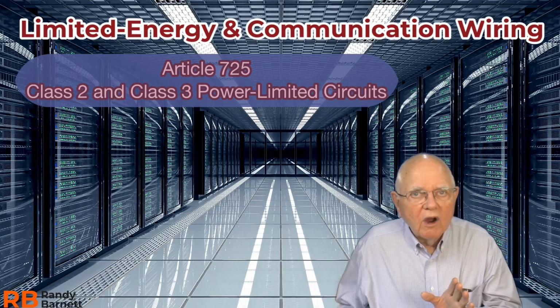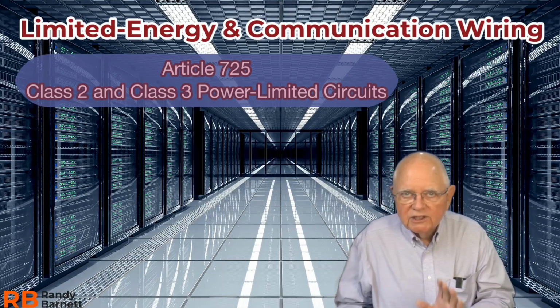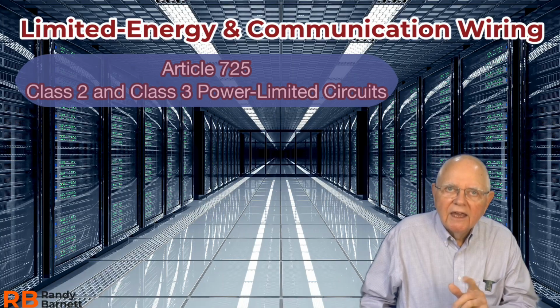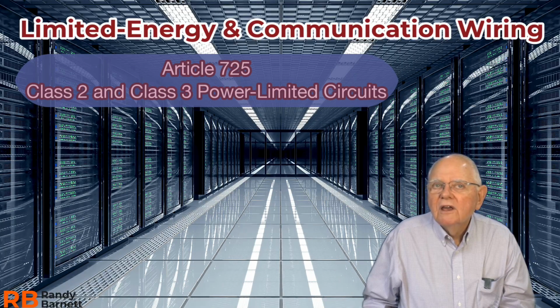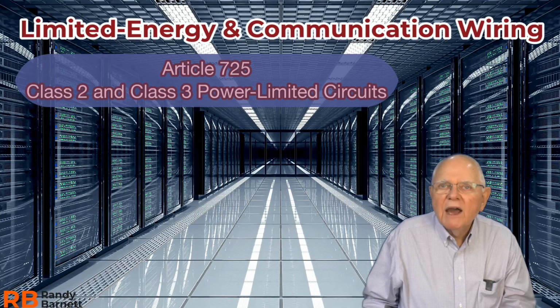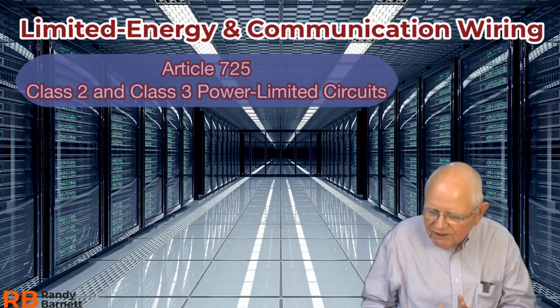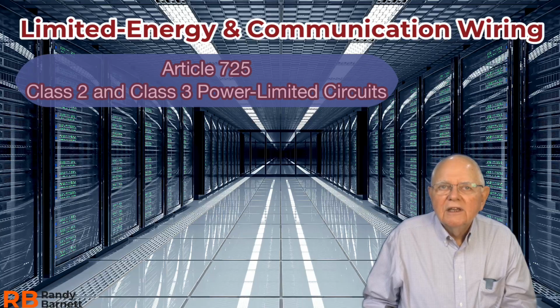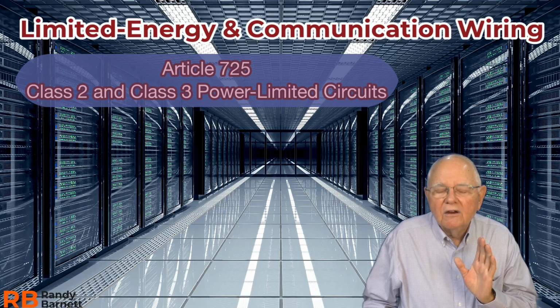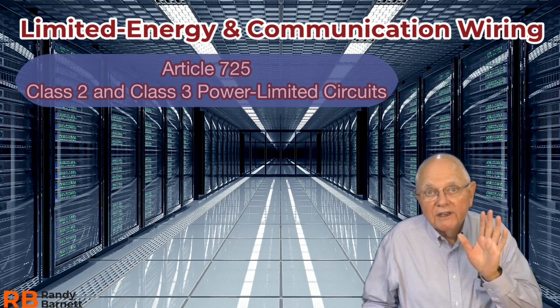Listing and marking requirements are required then, and it spells out those requirements in Article 725. Class 4, fault mitigated power systems are covered. Fault managed power systems are covered in the article as well. It's covered in the next article.